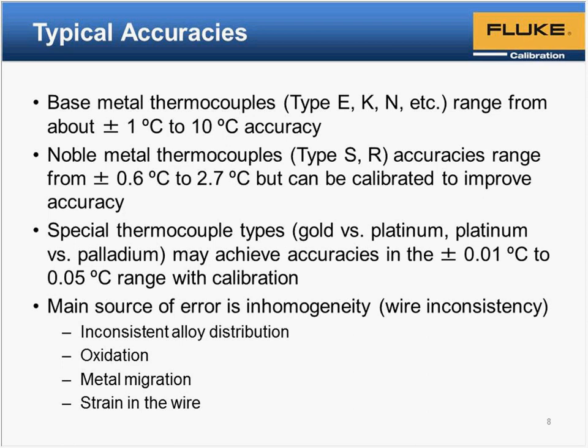And strain in the wire. Usually, in most cases, this isn't even noticeable, but it can cause a change in temperature reading. So if you have wire that's been strained, bent sharply, for example, it could cause the reading to change a little bit, or in some cases quite a bit.